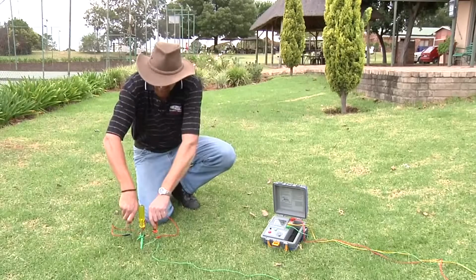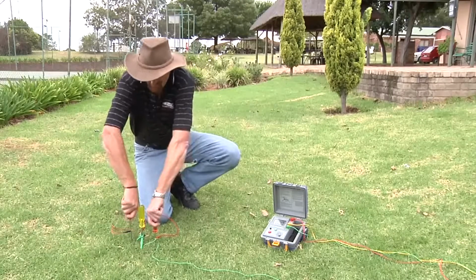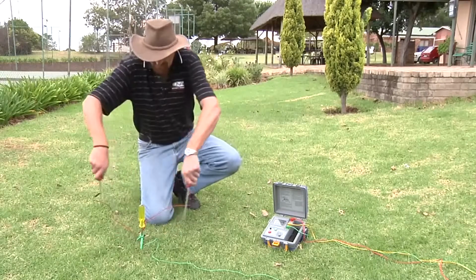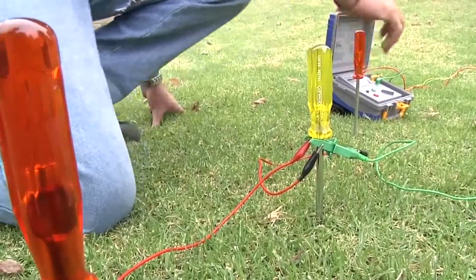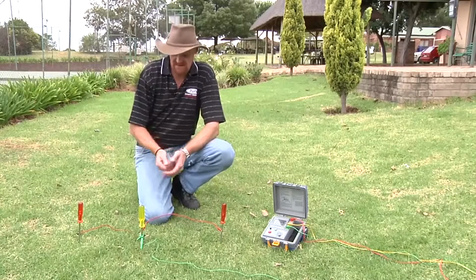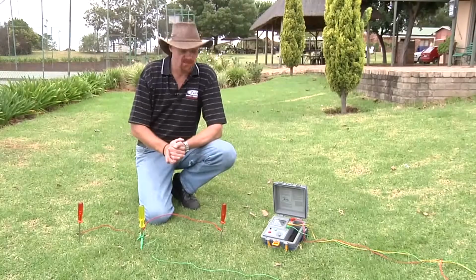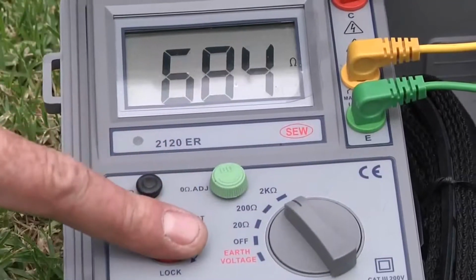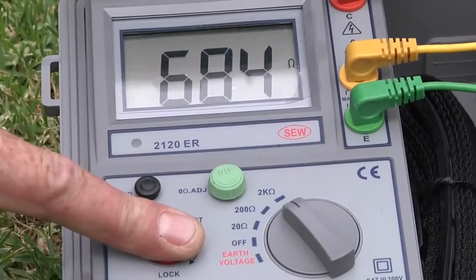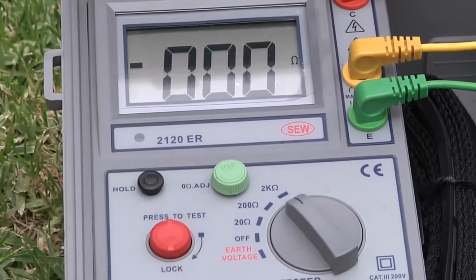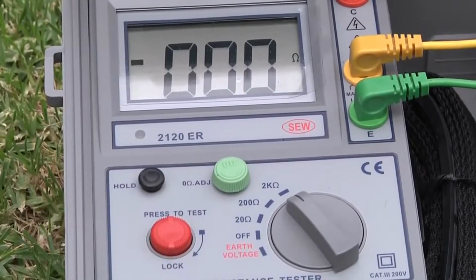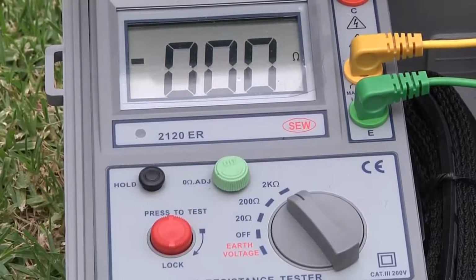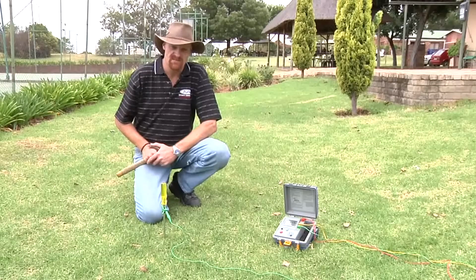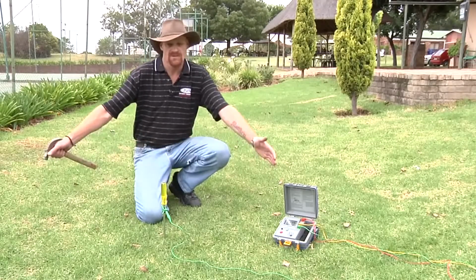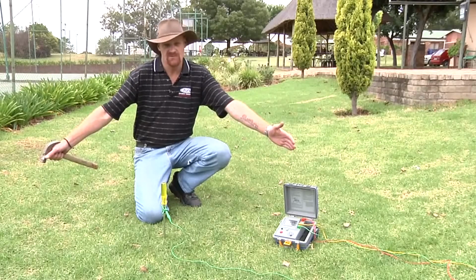Once we move the earth spikes further apart from each other, as in our 3 earth spikes, moving them 1.2 meters apart, we take a new reading. As we can see, the new test has much lower resistance, and as you know, lower resistance equals better conductivity. So our first demonstration showed the importance of having your earth spikes 1.2 meters apart.